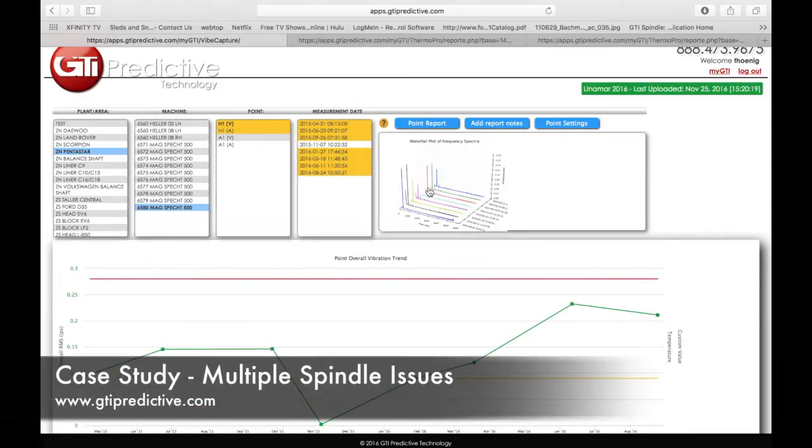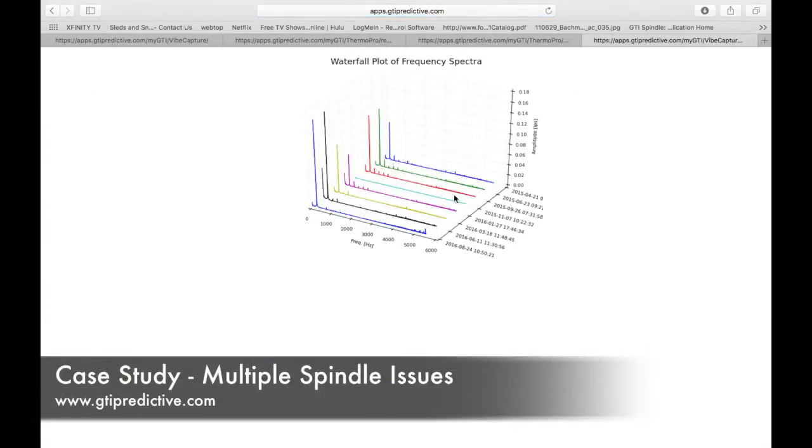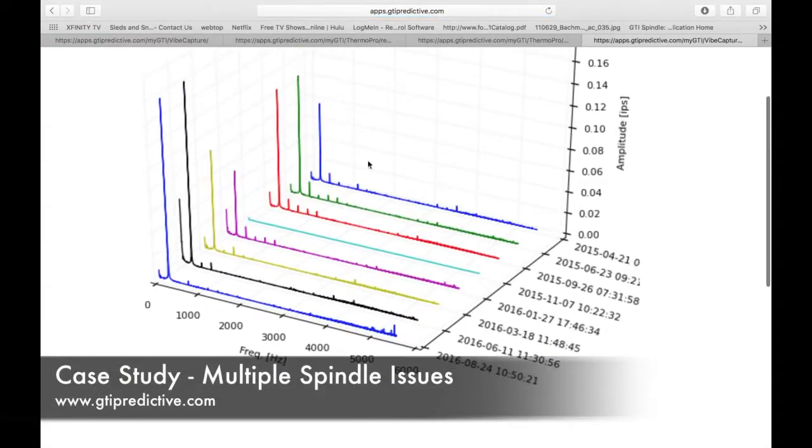Again, we're visited with a similar waterfall plot here that's showing us we're having a tooling imbalance problem that's coming and going, coming and going. I even see a false reading here. I can see that somebody took a blank reading which should probably be erased, but it's not troublesome at this point.